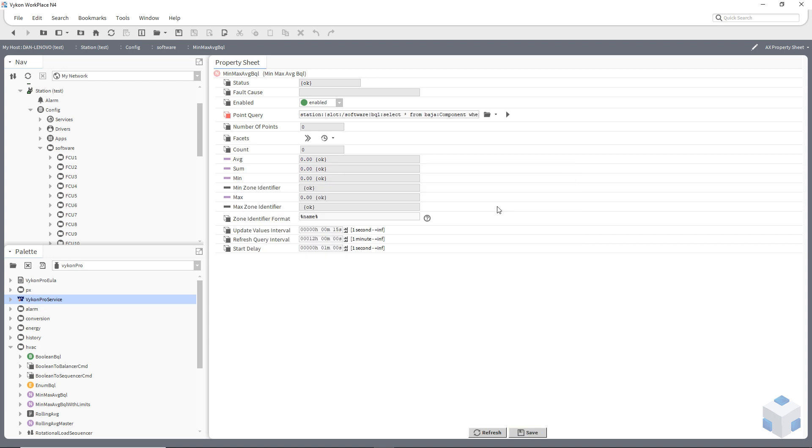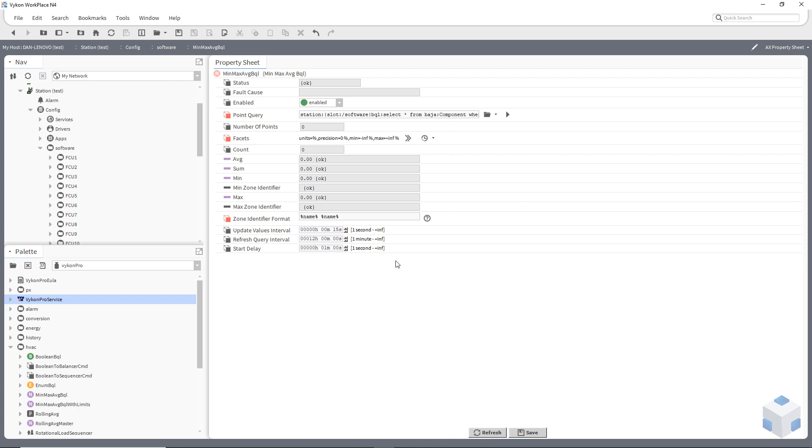I'm actually going to put a facet in there. I'm actually going to use a zone identifier because otherwise it would sit there and just say heating valve. Every single point is called heating valve. So I'm going to try and actually make the point a bit more unique. What I'm going to actually use is the parent name. So we'll actually be able to use the fan coil unit one, two, three, as well as what we're actually looking at within our naming convention. You'll see what I mean in just a second. So I'm going to go parent dot and save that.